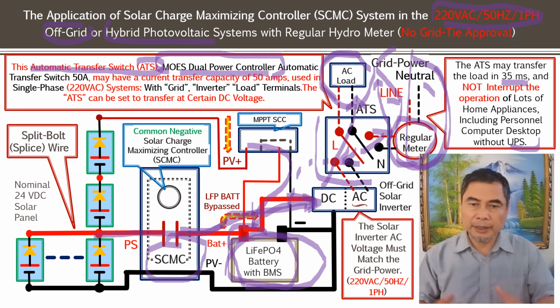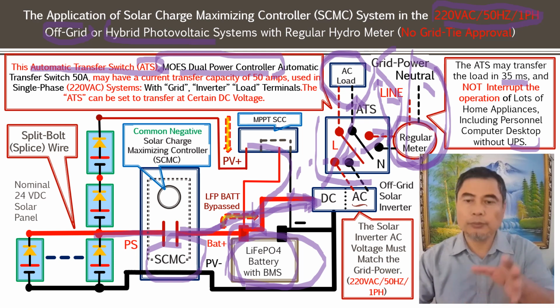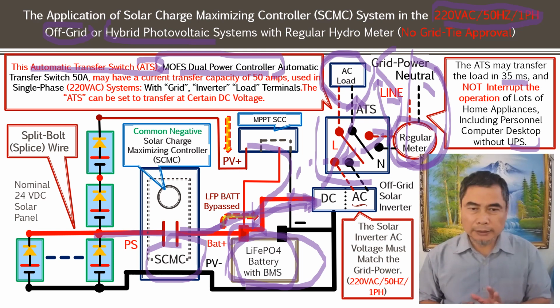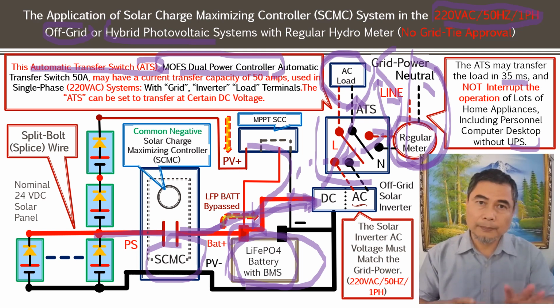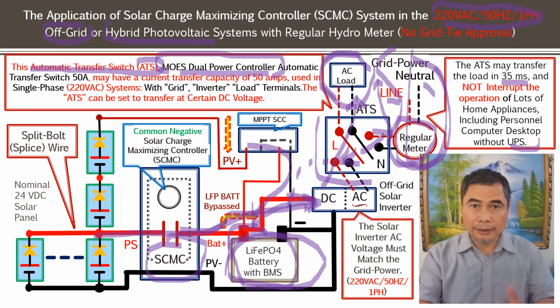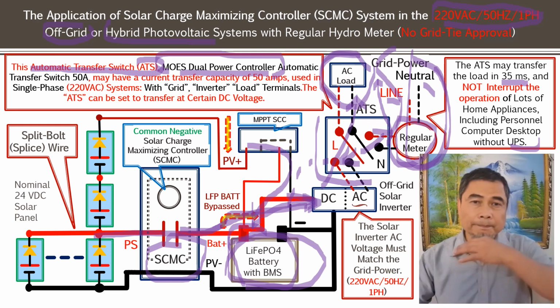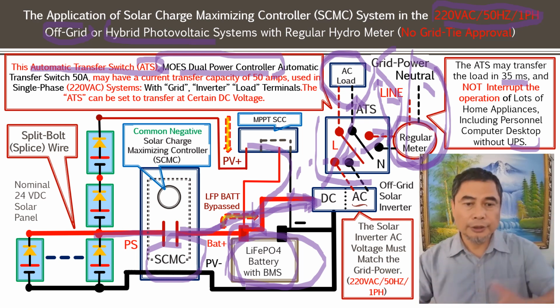You may have a gas generator here, just in case you do not have this kick in. But the setup would be different because you need time to do the transfer. The transfer switch you are using could be different. But this is the system with the grid power and PV system. We call it a hybrid photovoltaic system to power the load. The benefit of this system is to minimize the power draw from the grid, because normally during the daytime the utility company will charge more hydro rate during the day, right? Because they have an off-peak rate and then a peak rate. They charge you different rates based on the time of use. This system will save the hydro cost during the day when the sun comes up and the utility price is higher, you just use your own.